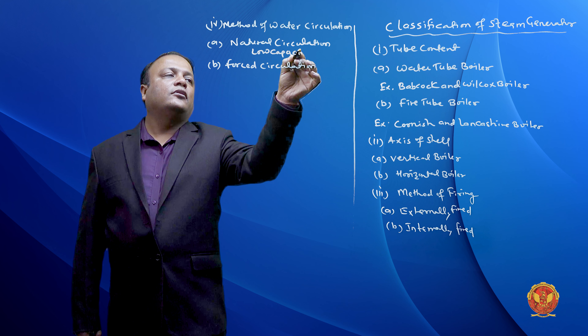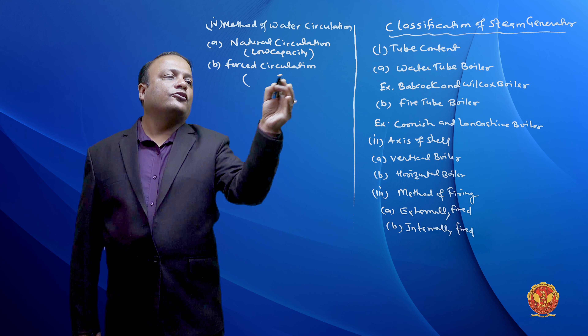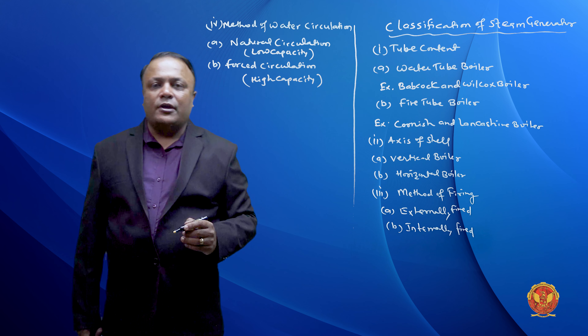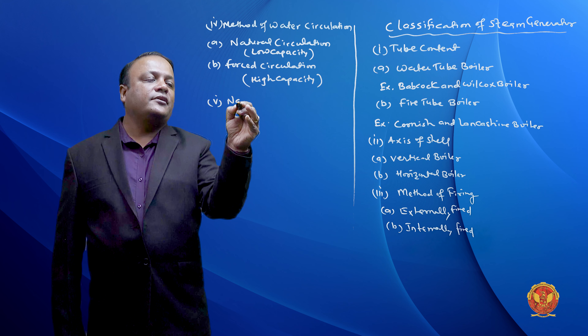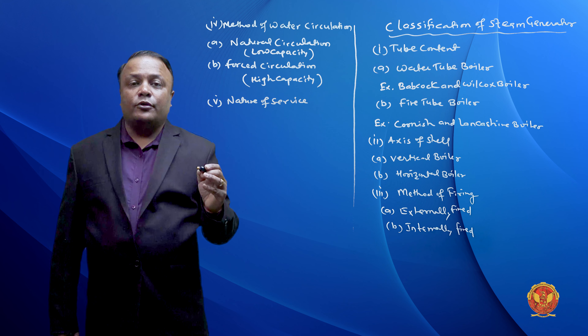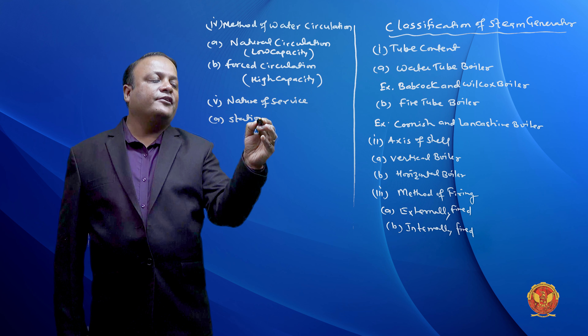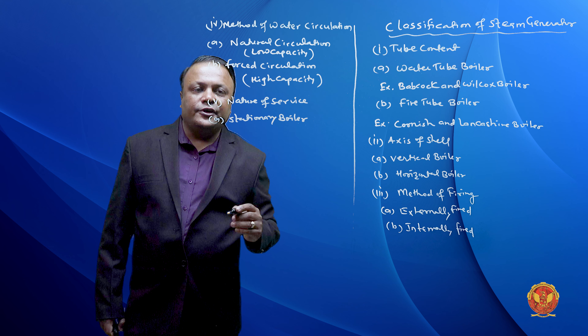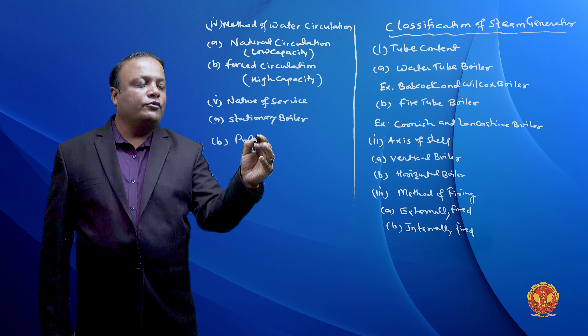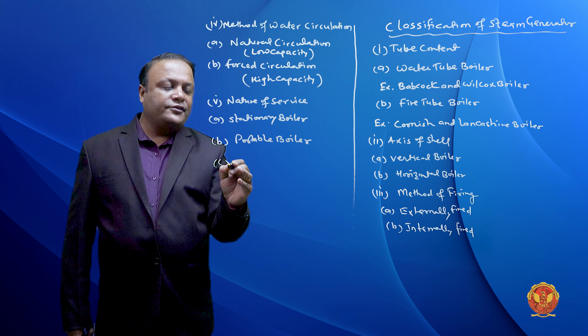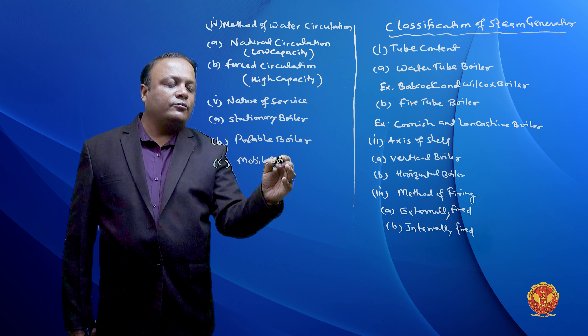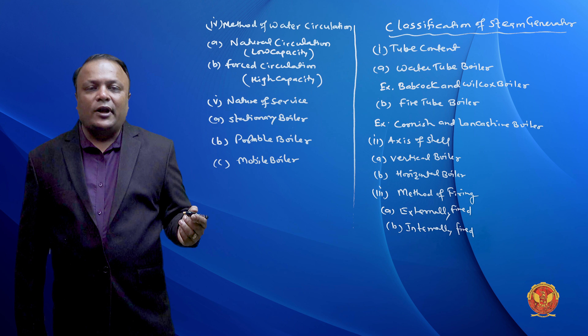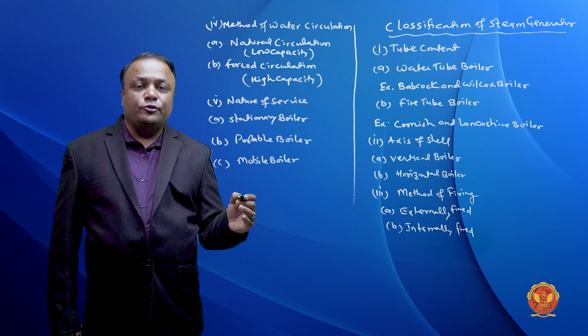The fourth classification is based on the method of water circulation inside the boiler. The first method is natural circulation, as seen in the Babcock and Wilcox type boiler, where water circulates without the help of any pump. The second is forced circulation, where a pump is used to force the water. Natural circulation is used in low-capacity boilers, while forced circulation is used in high-capacity power plants where a large quantity of steam is required.